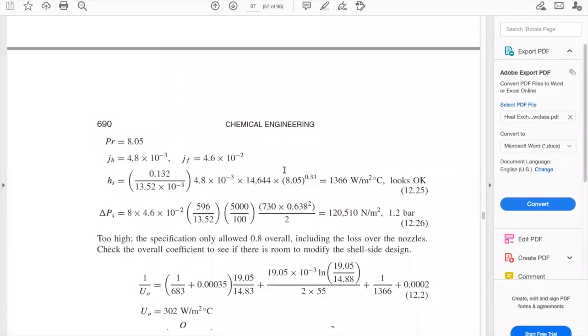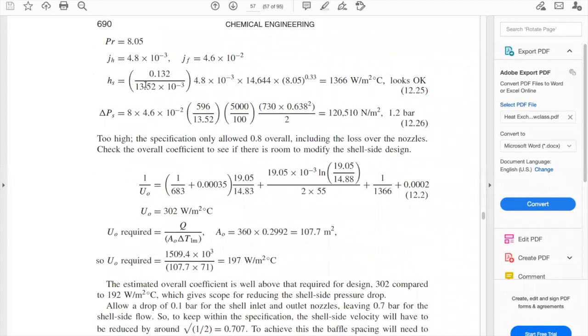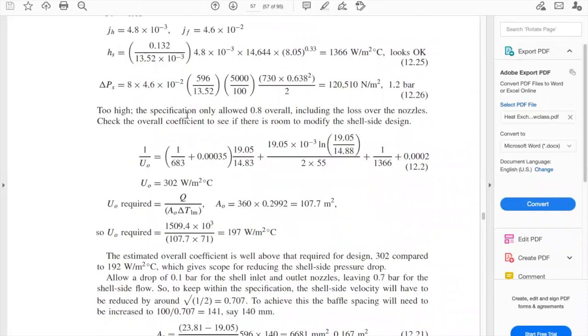After calculating, we have a delta P of 1.2 bars for the shell side. Again, this is higher than the specified 0.8 bars allowed for both the shell and the tubes. So we need to check the overall heat transfer coefficient to see if there is room to modify the shell side design.